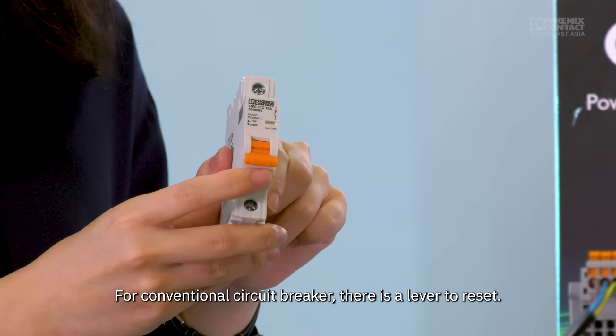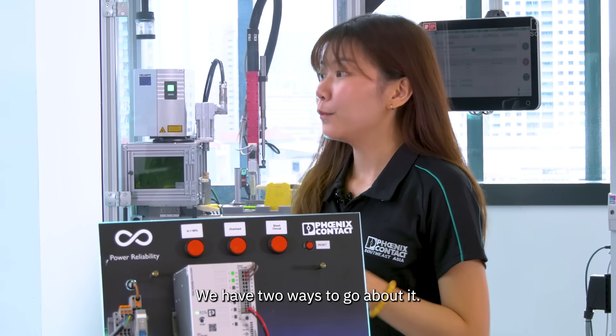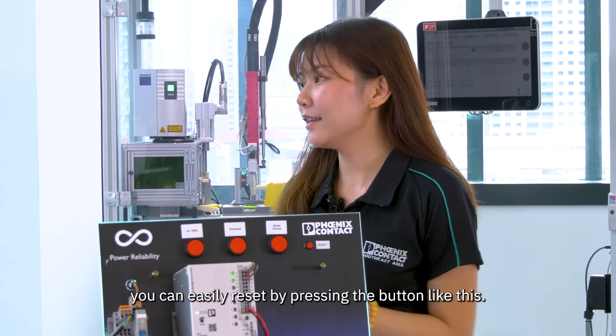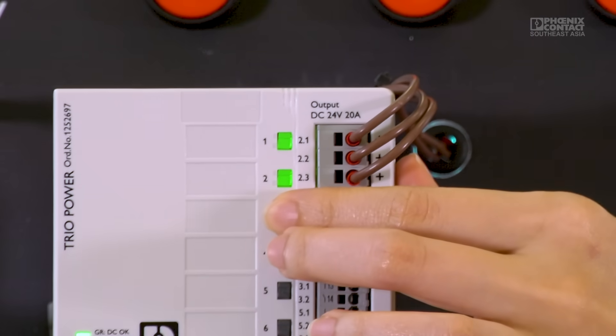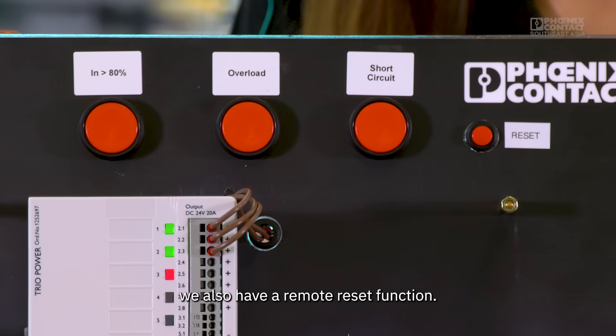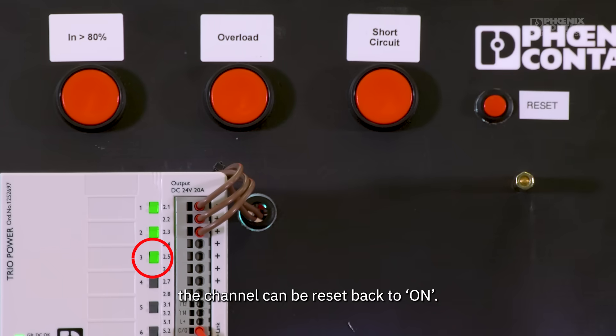For a conventional circuit breaker, there's a lever to reset. How do you reset your tripped channel? We have two ways to go about it. Firstly, if you are physically at the panel, you can easily reset by pressing the button like this. But with our TRIO POWER, when there's a short circuit, we also have a remote reset function. So when you give a 24V signal to the terminal, the channel can be reset back to on.